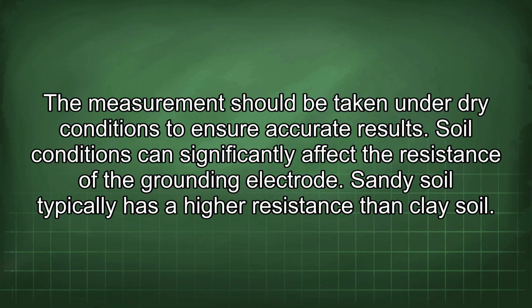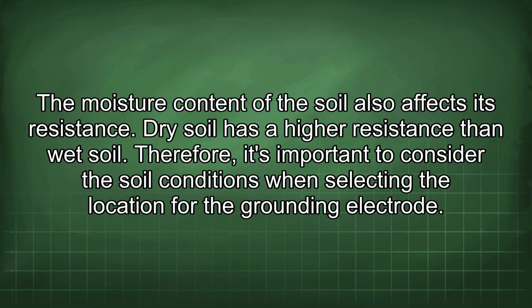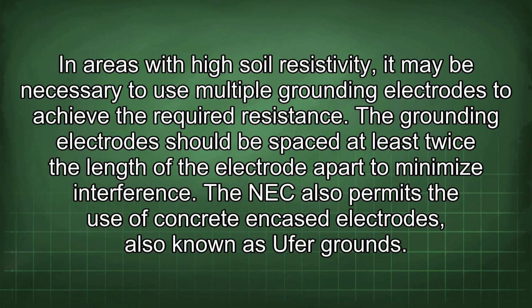Soil conditions can significantly affect the resistance of the grounding electrode. Sandy soil typically has a higher resistance than clay soil. The moisture content of the soil also affects its resistance. Dry soil has a higher resistance than wet soil. Therefore, it's important to consider the soil conditions when selecting the location for the grounding electrode. In areas with high soil resistivity, it may be necessary to use multiple grounding electrodes to achieve the required resistance. The grounding electrodes should be spaced at least twice the length of the electrode apart to minimize interference.